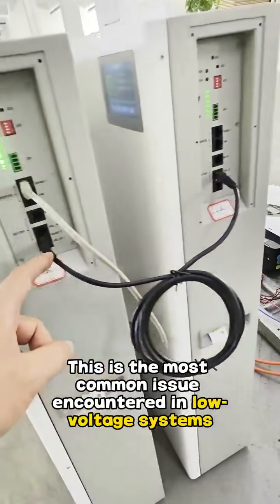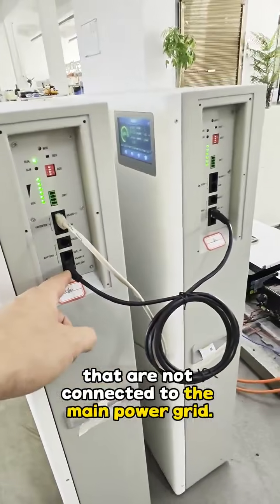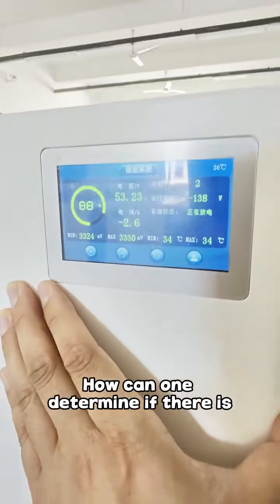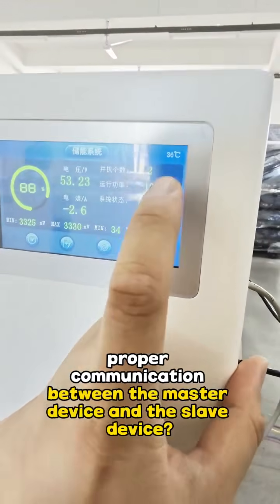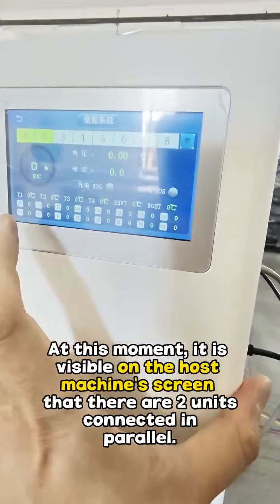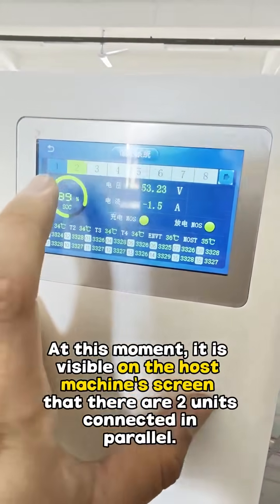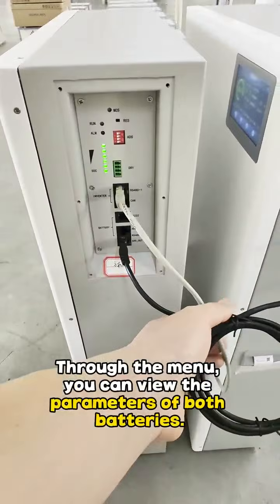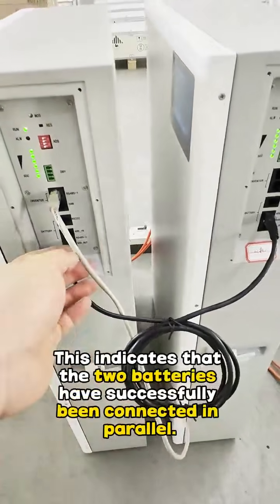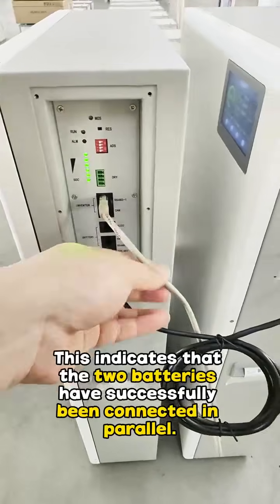This is the most common issue encountered in low-voltage systems that are not connected to the main power grid. How can one determine if there is proper communication between the master device and the slave device? At this moment, it is visible on the host machine screen that there are two units connected in parallel. Through the menu, you can view the parameters of both batteries. This indicates that the two batteries have successfully been connected in parallel.